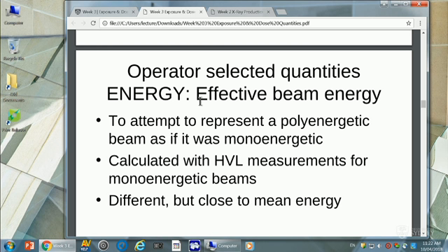But instead of now saying, well, we're giving the same because I've given 70 and 30, he's given 70 and 30, what you will be saying is, you'll be finding your 2.1 or whatever I said it was, and you'll be saying 2.1 millimeters of aluminium equivalent actually gives me an effective beam energy of 66, whereas this guy's giving 2.4 and he's getting 73. So now we've got a much more honest appraisal of the different energies. So what you're doing is you're simplifying the half-value layer in your unit, going to the table, finding that half-value layer, and then just pulling up the effective beam energy that matches it.